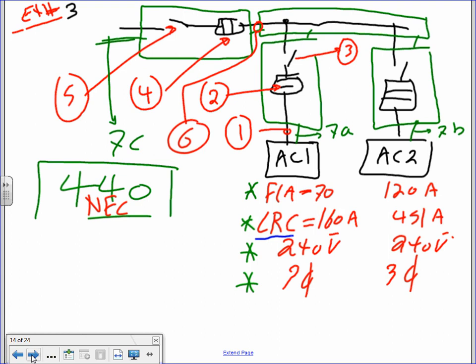If you remember when we went to Boston Scientific — did you see those VFDs right on the chillers? They have tons of VFDs on the chillers, designed by the manufacturer. That's why as design engineers, don't mess with these. Typically all you need to provide is a fuse disconnect, and sometimes the manufacturer even provides the disconnect right at the chiller. All you need to provide is just the branch circuit cable.